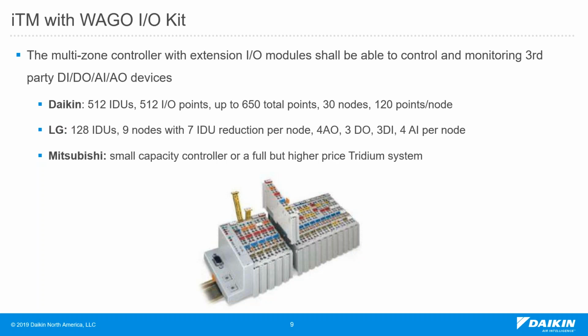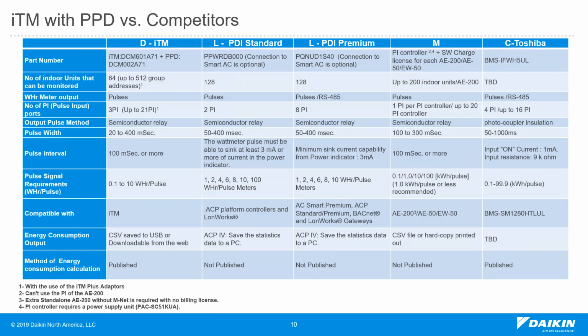So Mitsubishi system, they do not have extended I/O module that can add to their centralized controller, but they have to use Tridium system. So with Tridium system, they add their JACE, and after that they add their I/O module, and then all of this data will be into the JACE. So that's how we compare integration between our ITM to the Wago I/O kit.